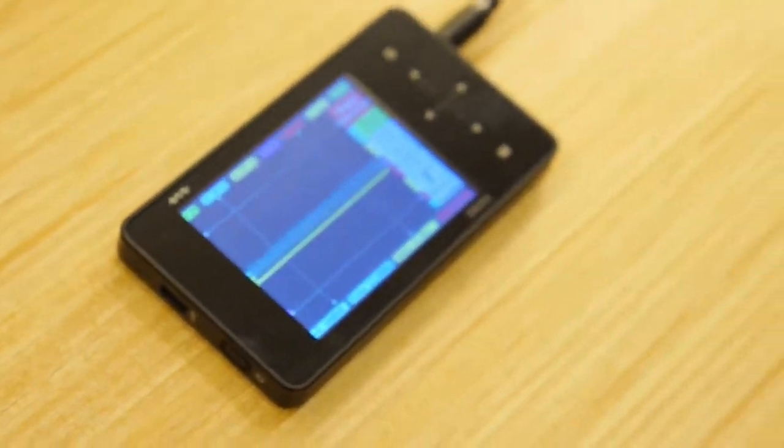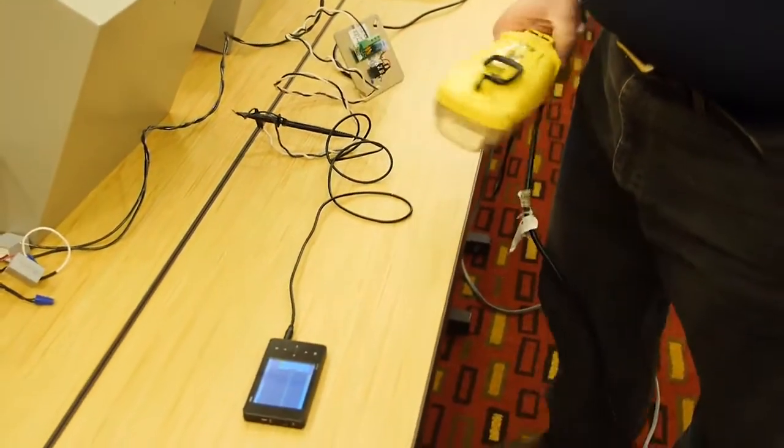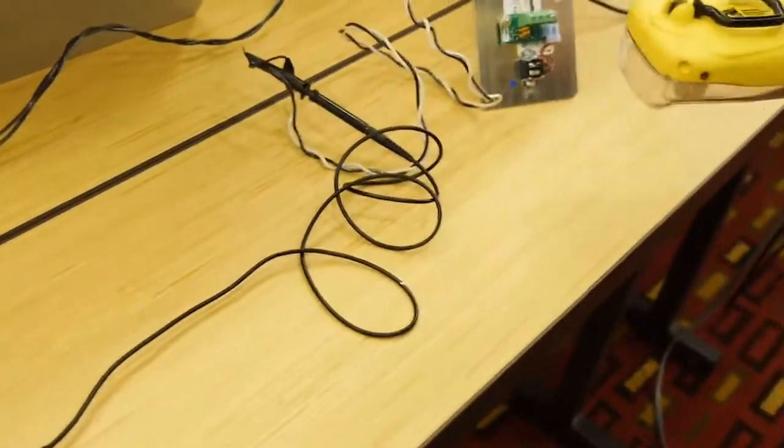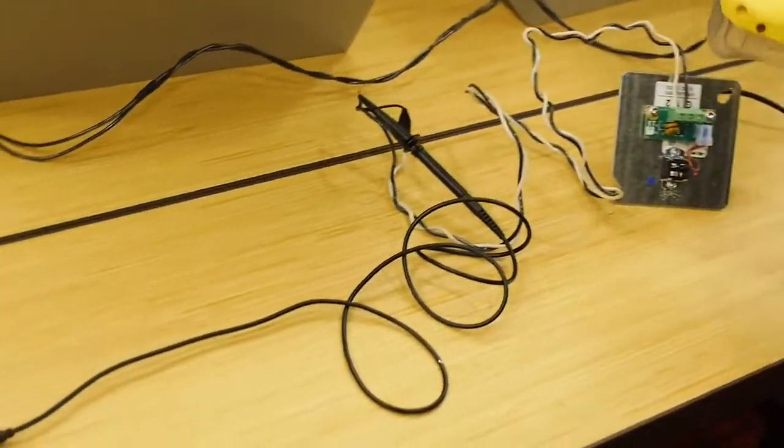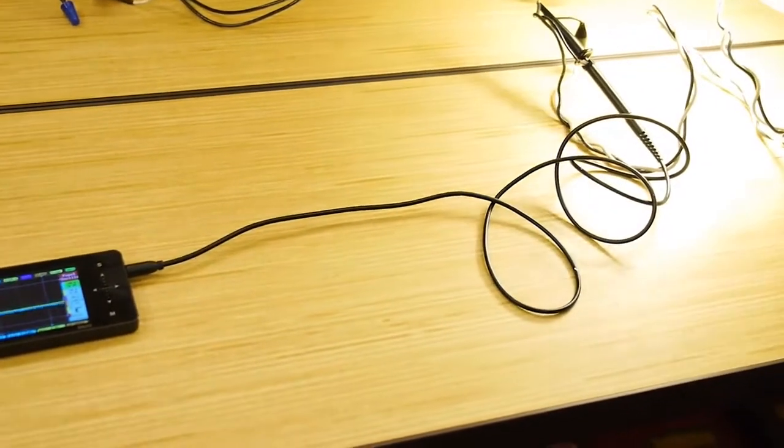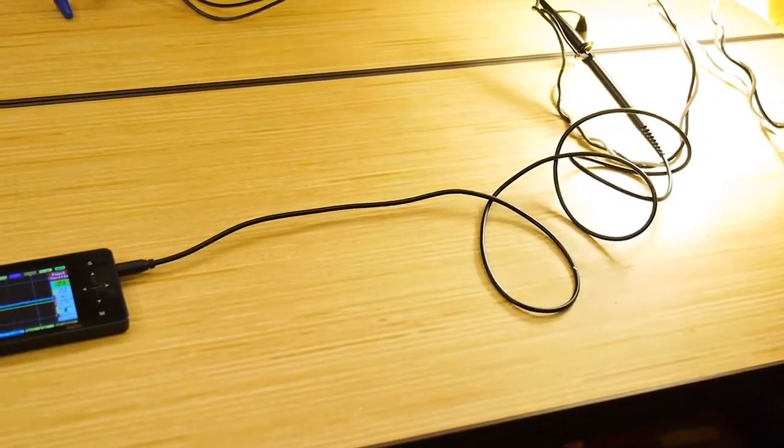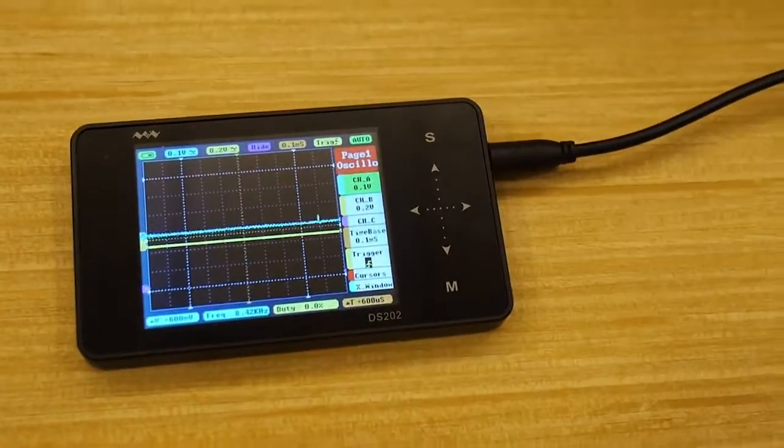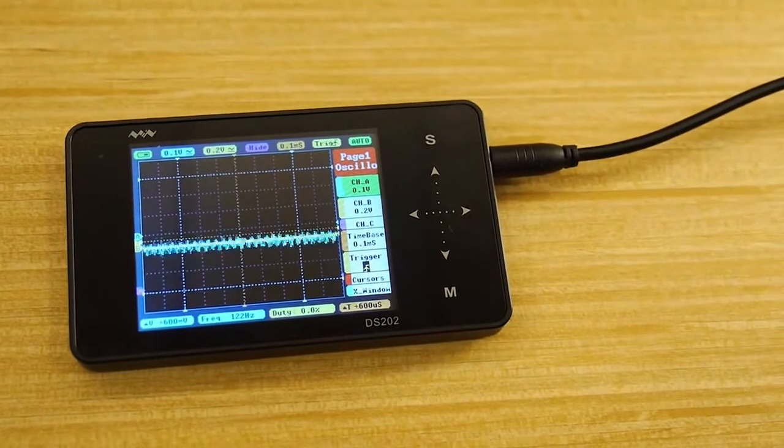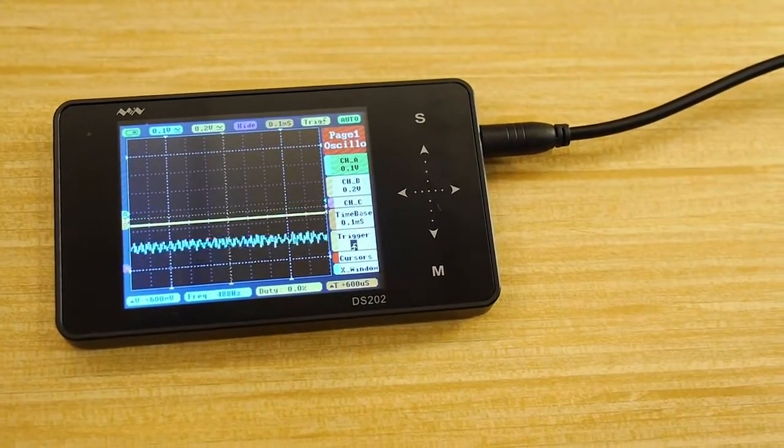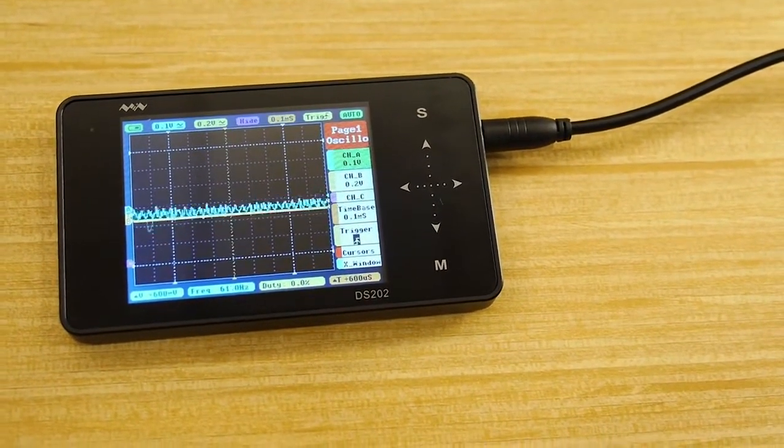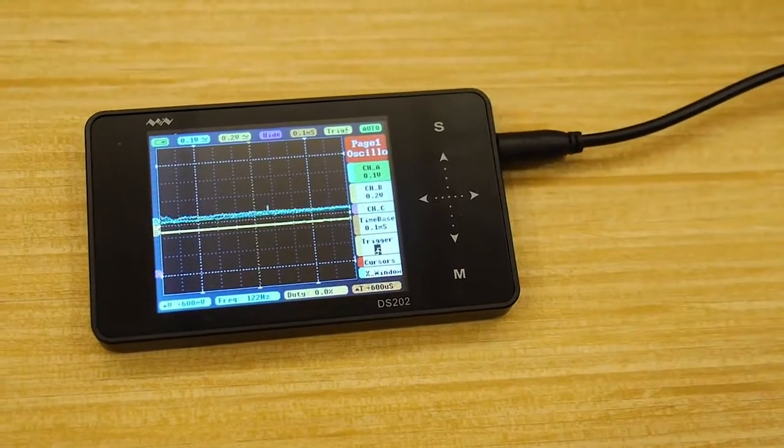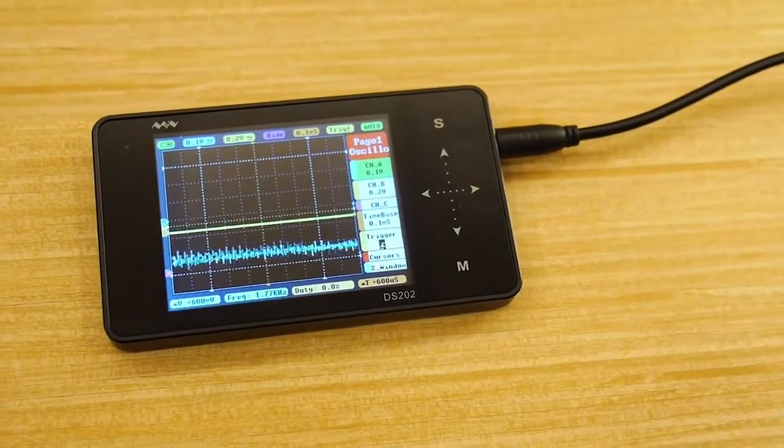All that noise means we could be losing the signal in our site controller or communication between our PCM boards, DPC, or anything else could be failing. We are currently using a shielded PetroNet wire from the junction box. So even with the shielded wire, we're still picking up some noise from the fluorescent light. If you're running wire in a gutter box with other high powered wire, anywhere near lights, any of that kind of stuff, this is the kind of noise that could be affecting the operation of the system.